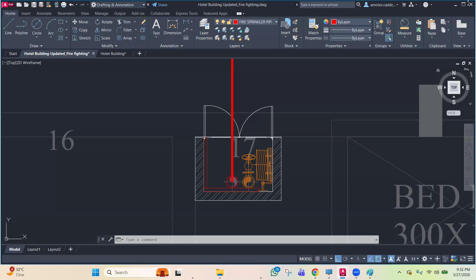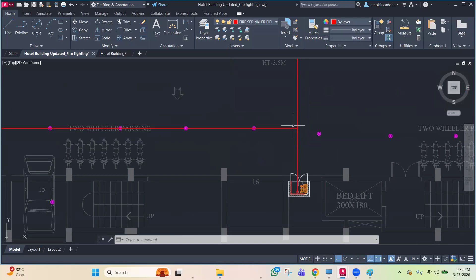See, first of all, as water flows along a pipe in a normal sprinkler system, the flow keeps on reducing because water is discharged at each sprinkler, so the required pipe size also reduces. At the start of the sprinkler line, the flow will be high, so a bigger pipe is used, and towards the end sprinkler, a smaller pipe is required. This is based on hydraulic calculation, flow and pressure losses. Now, if you see in the curtain system, all the nozzles discharge at the same time.